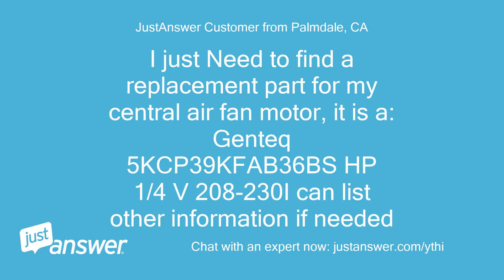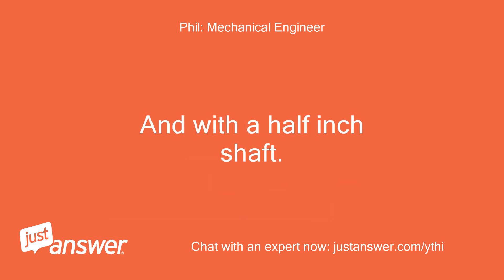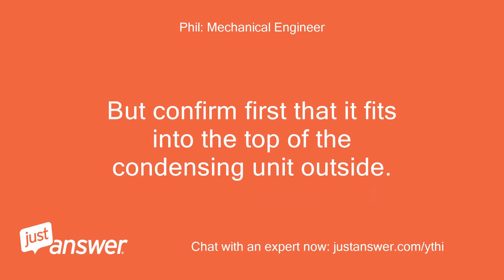I just need to find a replacement part for my central air fan motor. It is a Genteq 5KCP39KFAB36BS, HP 1/4, V 208-230. It looks like a 1050 RPM single-speed condenser fan motor that has two brown wires running to a 5 or 6 microfarad run capacitor, and with a half-inch shaft. If that is the case you can buy a replacement at Grainger Industrial Supply for about $150 or a bit less — mark the direction of rotation on it and take it in for a matchup. But confirm first that it fits into the top of the condensing unit outside.